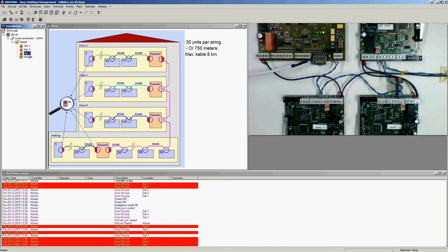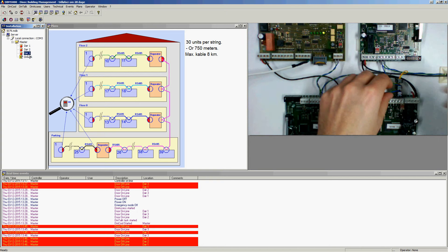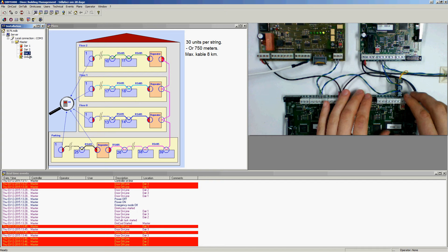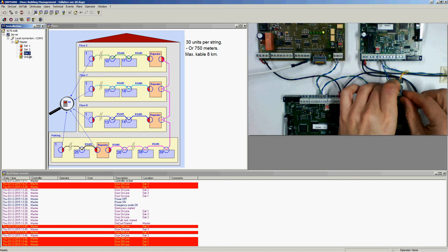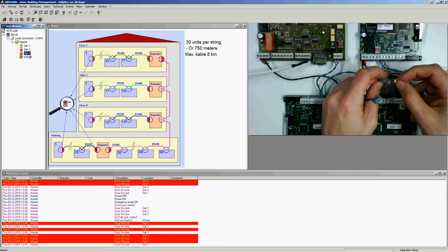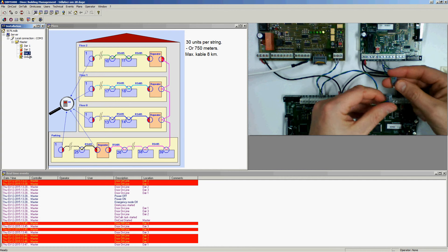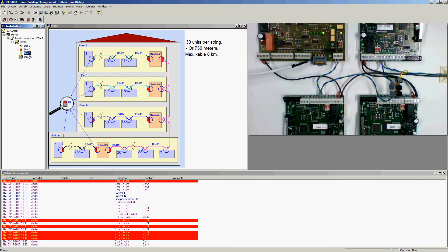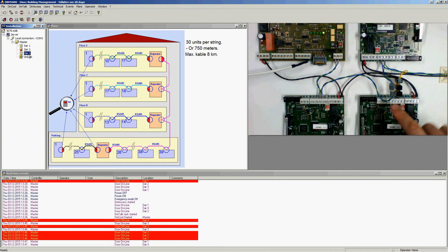Because you just can't do it without taking something off. If I know it's this door that is making the error, I could just take off these connectors, make a small bridge, and then bypass the door. We can immediately see that we have communication to the other doors. But if this chip is not burned to make a short circuit, it could also be not communicating at all — burned thoroughly, so there's no connection to the chip. Then this door would just remain without contact.